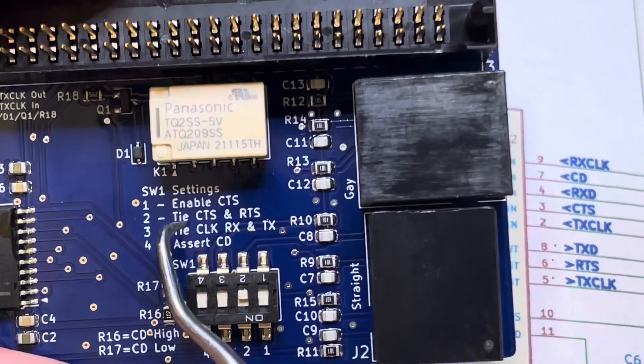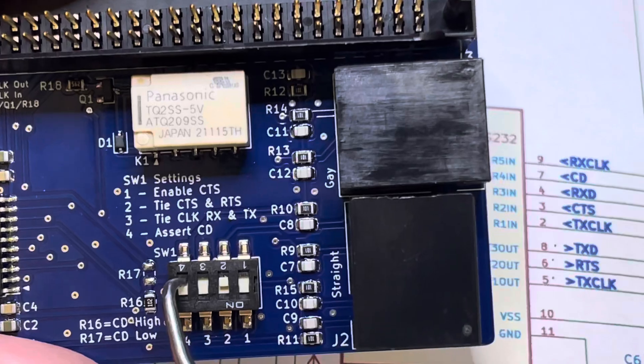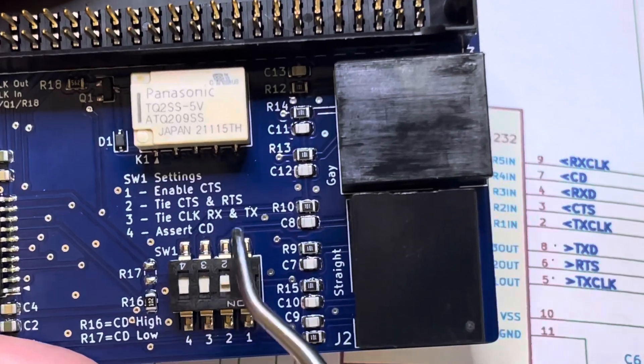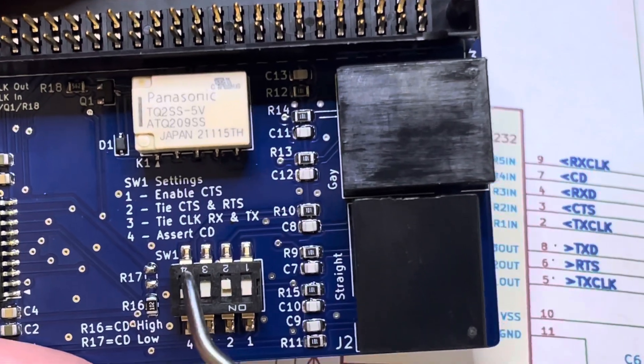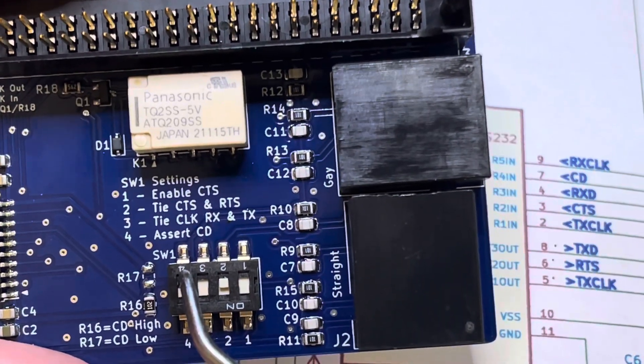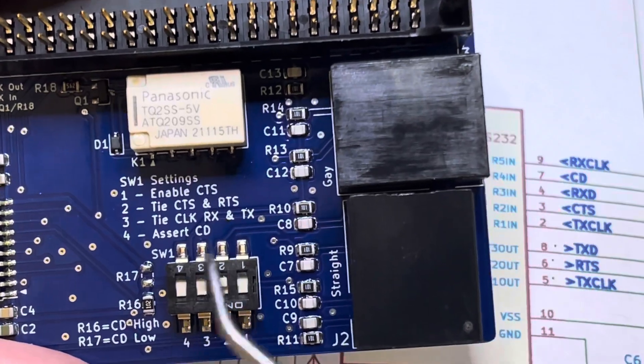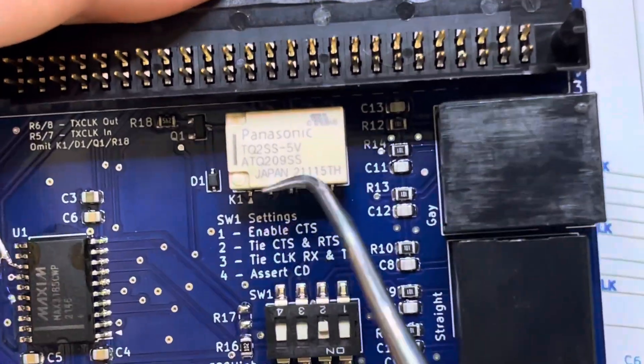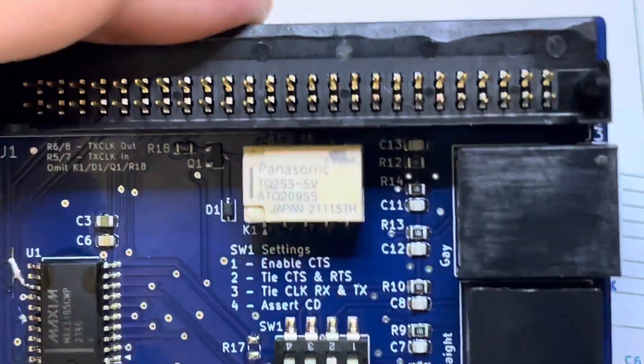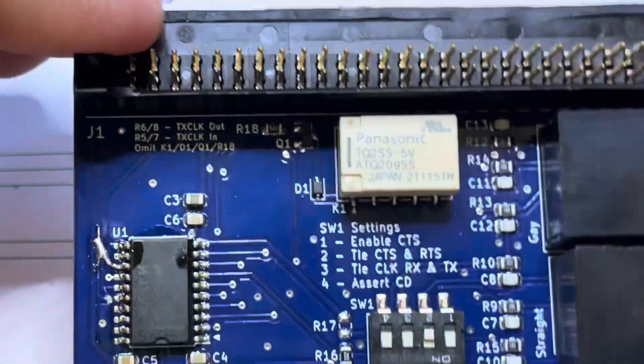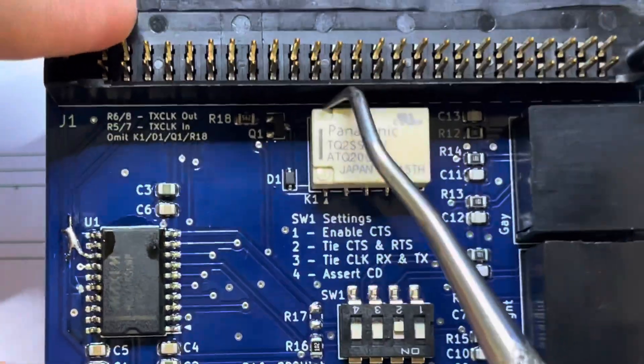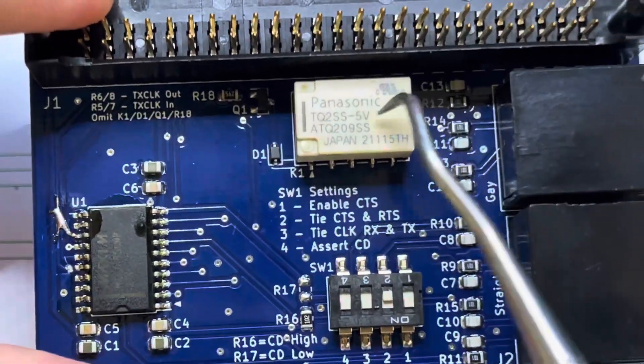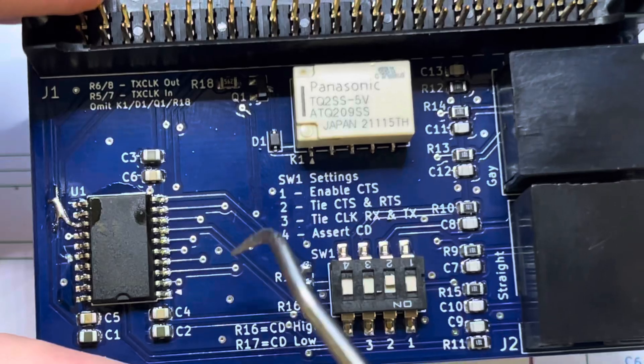If you do go into an Astrotack, it does care about carrier detect, it needs to be asserted, and the way this works it'll assert it on one end or the other. However, there's jumpers under all these if you want to eliminate this and just have it do one thing.